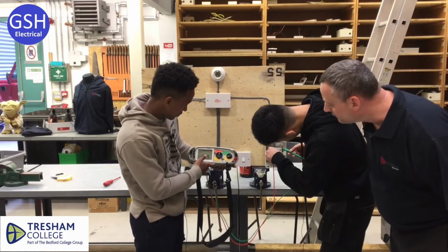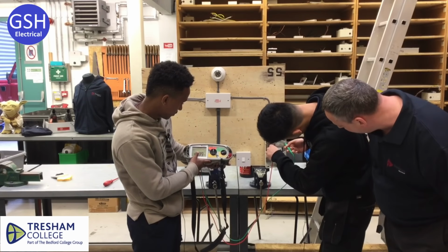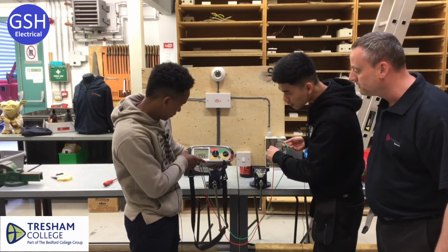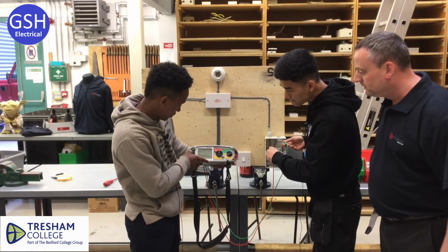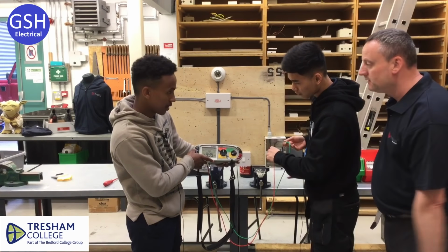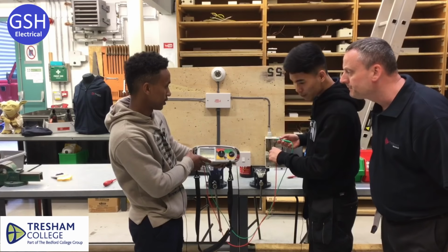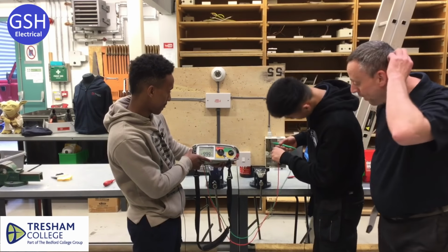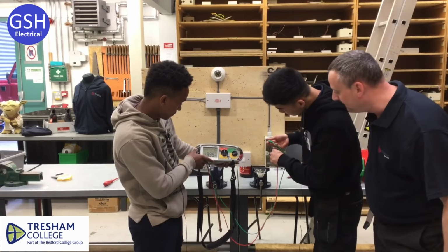So we've set it to 500 volts. We're in the red scale. Once you've probed on, I think Bill's going to press the button for us. Press and hold. And we've got a reading: 999, greater than 999. What's the smallest acceptable again? 1 mega ohm. We're way over it. We're off the scale of the machine, so we wouldn't expect to be anywhere near 1 mega ohm.